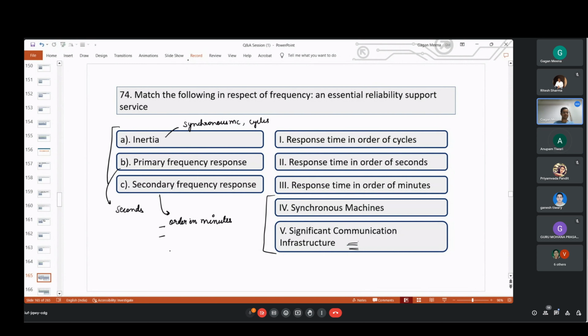We just discussed the slides back. Primary - no, no, not primary. Significant communication infrastructure - secondary, oh this is AGC control. The AGC requires communication. This is based on governor action. And this is inherent inertia within the rotating mass.